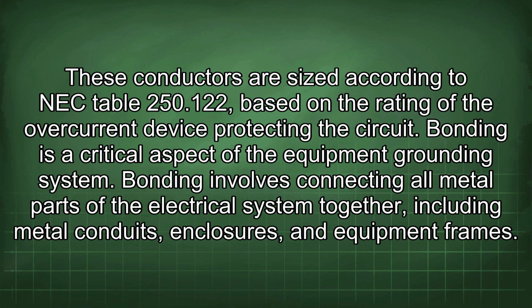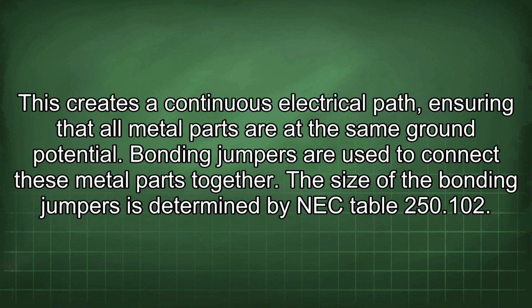Bonding is a critical aspect of the equipment grounding system. Bonding involves connecting all metal parts of the electrical system together, including metal conduits, enclosures, and equipment frames. This creates a continuous electrical path, ensuring that all metal parts are at the same ground potential. Bonding jumpers are used to connect these metal parts together. The size of the bonding jumpers is determined by NEC Table 250.102.